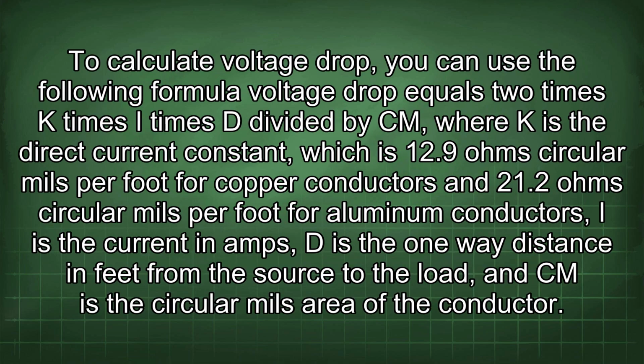To calculate voltage drop, you can use the following formula: voltage drop equals 2 times K times I times D divided by Cm, where K is the direct current constant, which is 12.9 ohms circular mils per foot for copper conductors and 21.2 ohms circular mils per foot for aluminum conductors. I is the current in amps, D is the one-way distance in feet from the source to the load, and Cm is the circular mils area of the conductor.